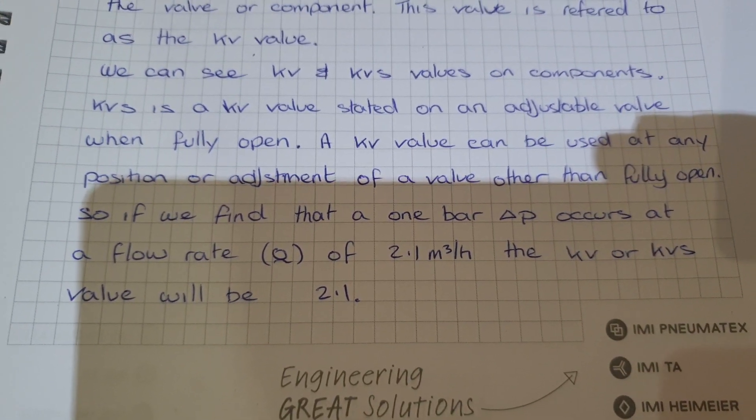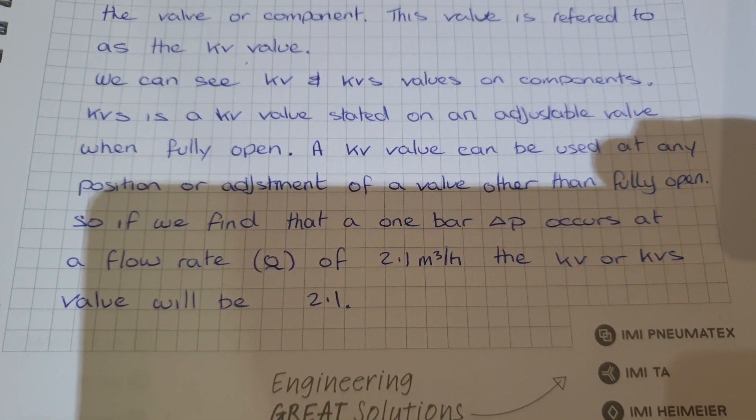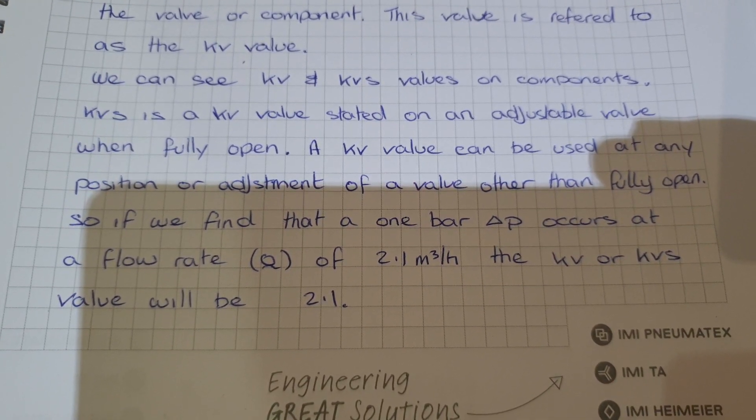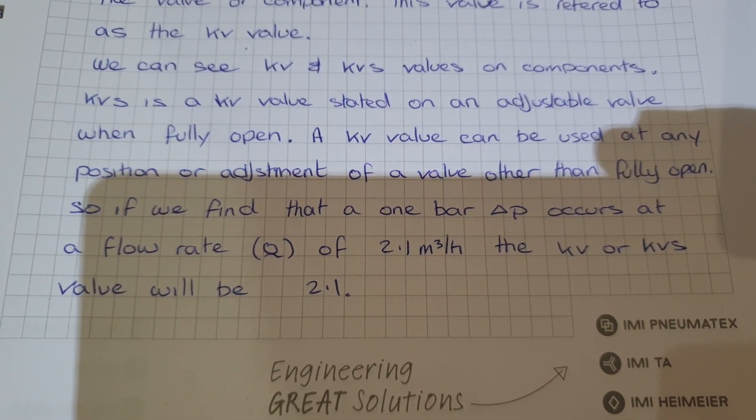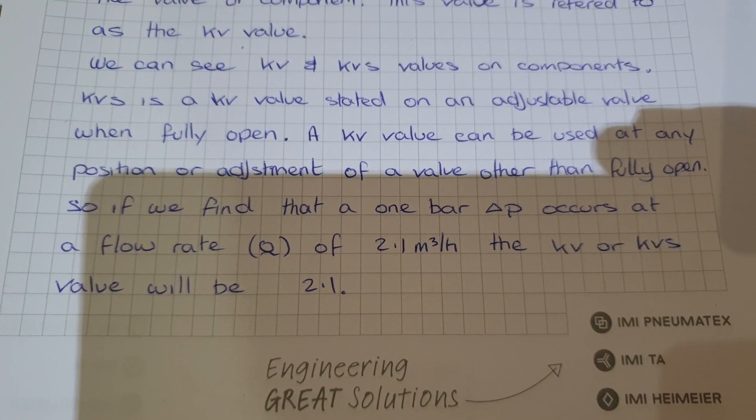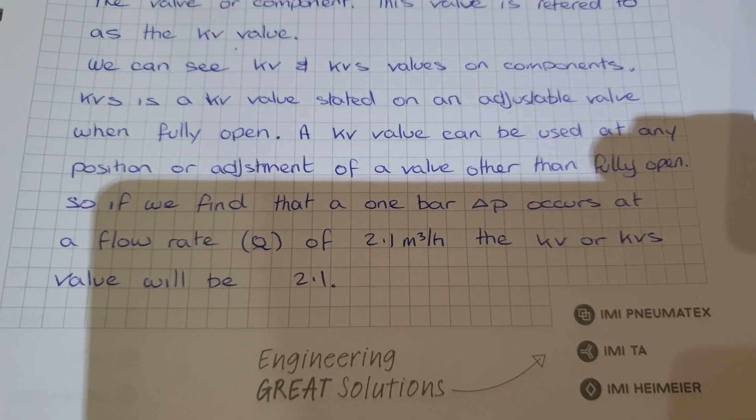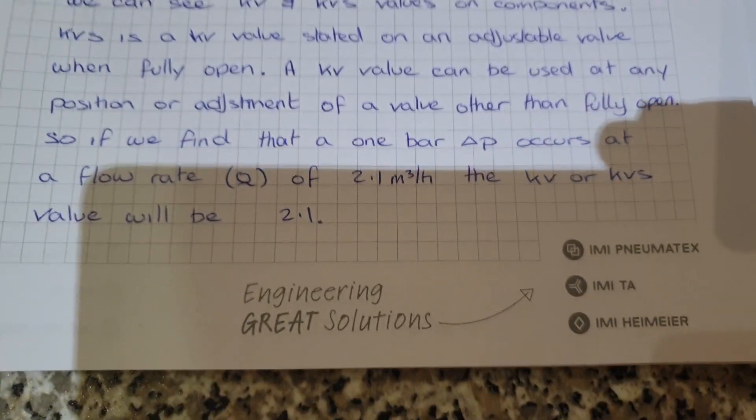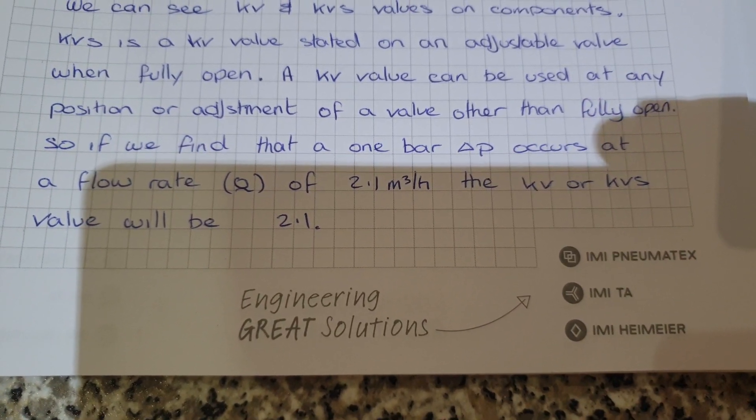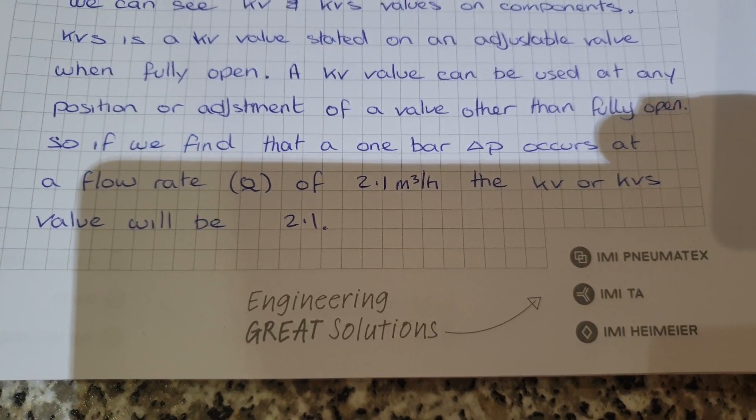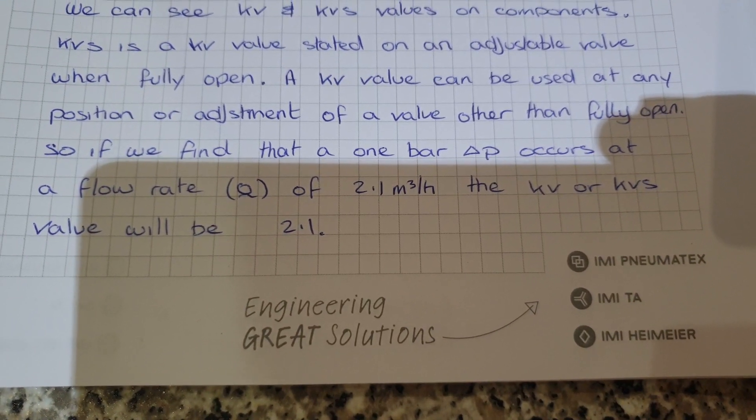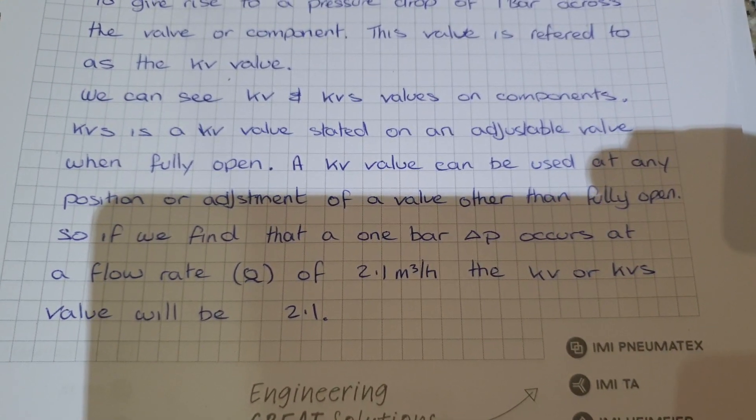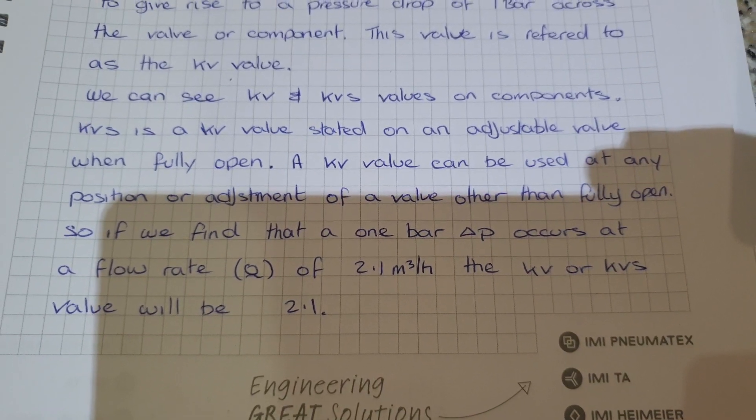We can see KV and KVS values on components. KVS is a KV value stated on an adjustable valve when it's fully open. A KV value can be used at any position or adjustment of a valve other than fully open. So if we find that a one bar delta P occurs at a flow rate of 2.1 cubic meters an hour, the KV or KVS value will be 2.1.